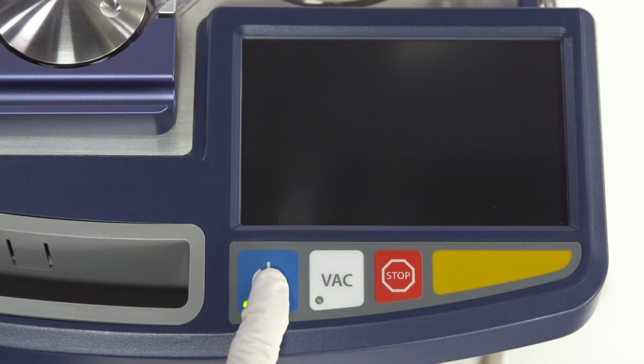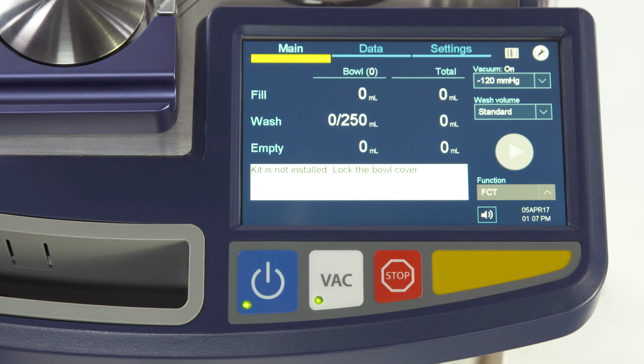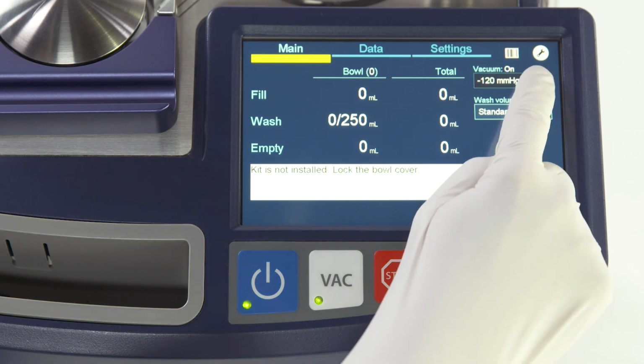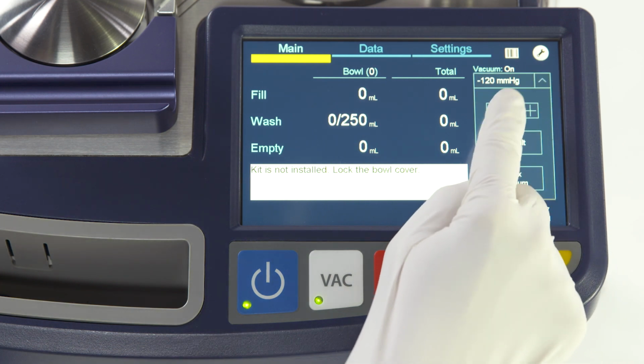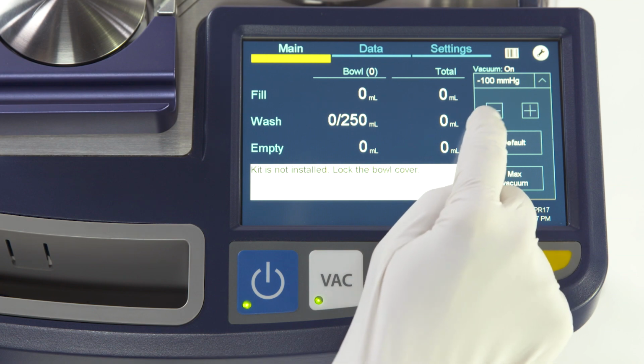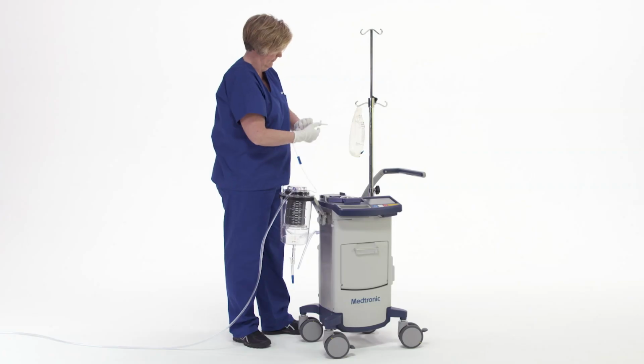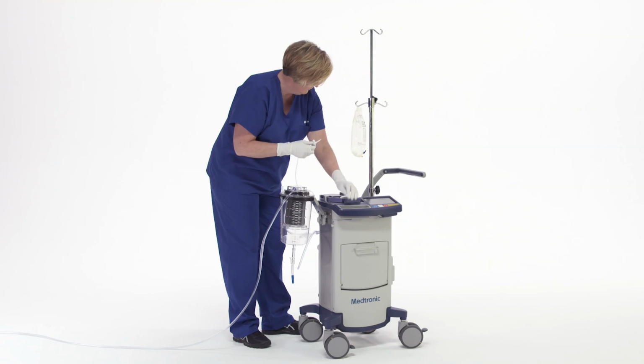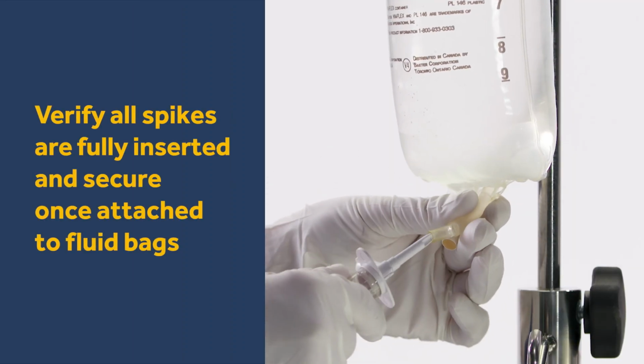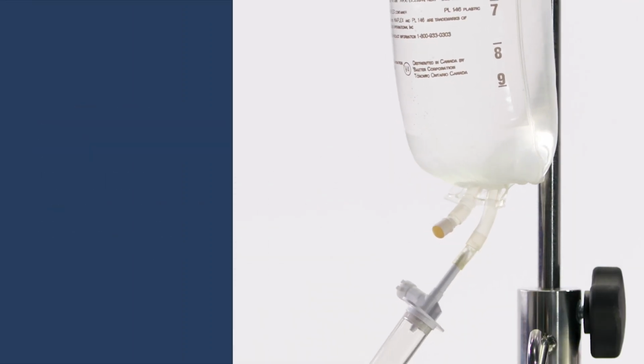Next, turn on the power by pressing the power button, and turn on the vacuum by pressing VAC. If necessary, you can adjust the vacuum setting by using the vacuum drop-down menu on the main screen. Next, spike the anticoagulant container. If the container is non-vented, open the vent cover on the drip chamber.